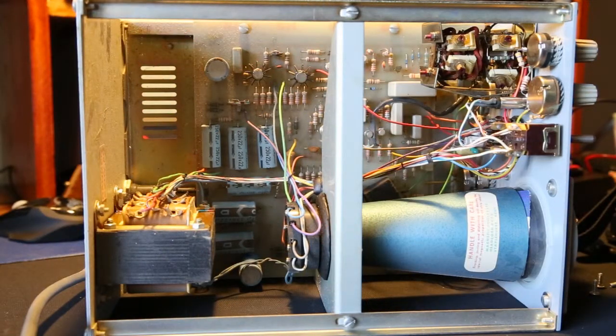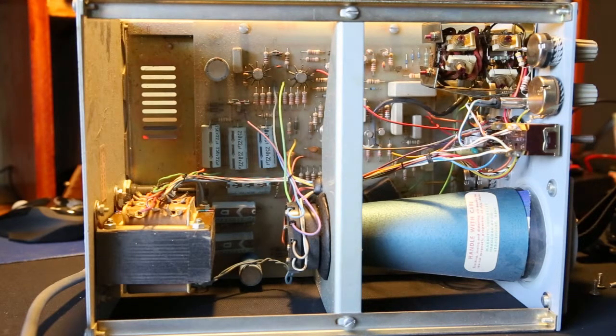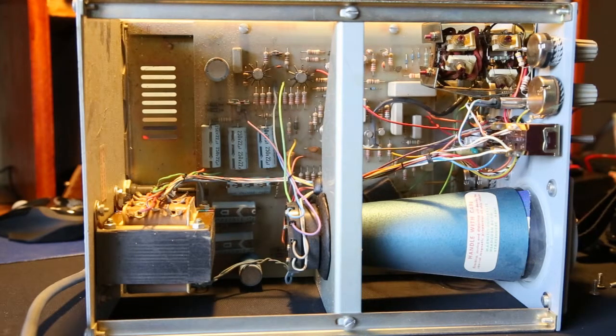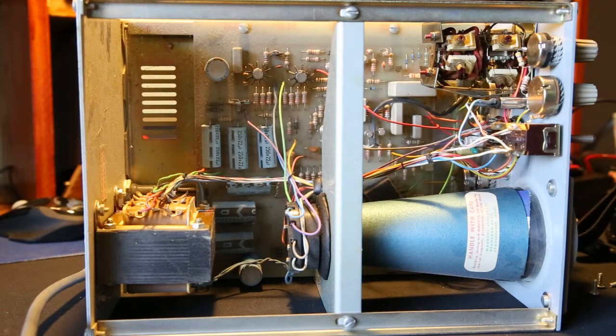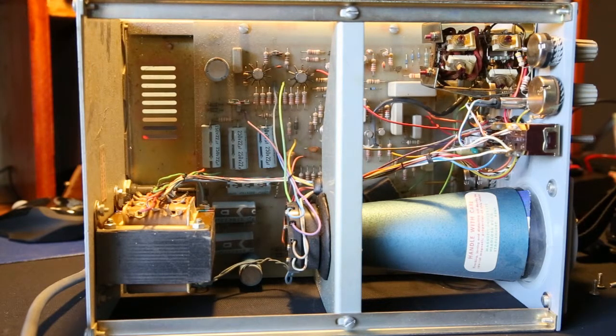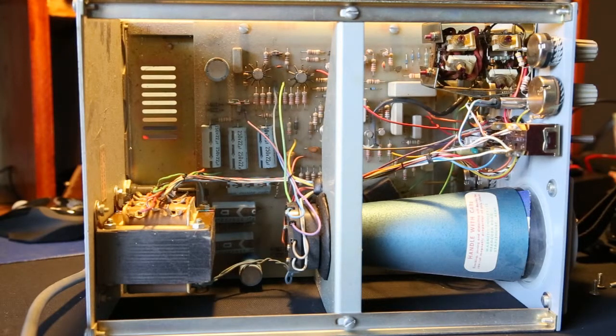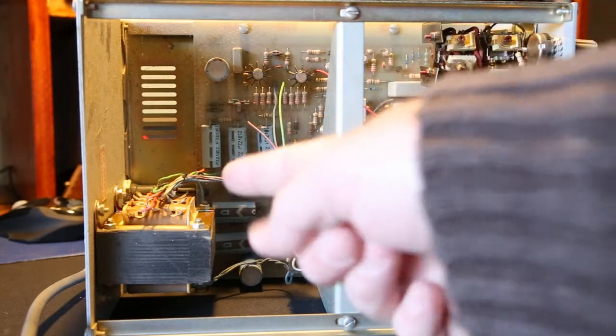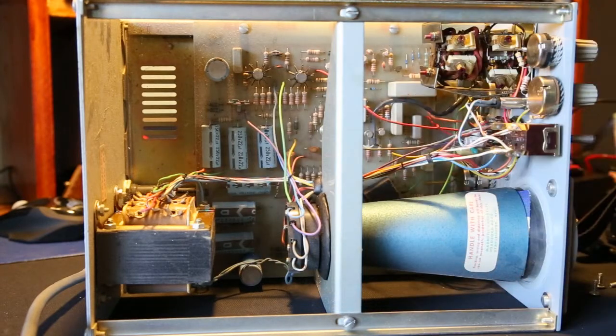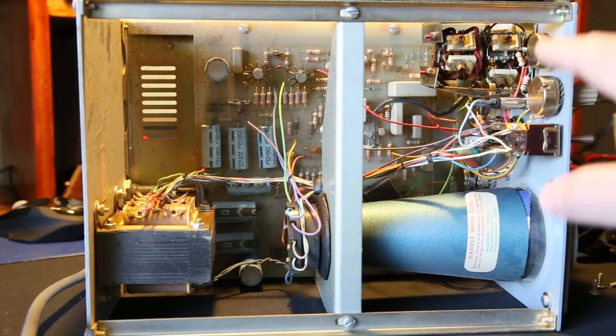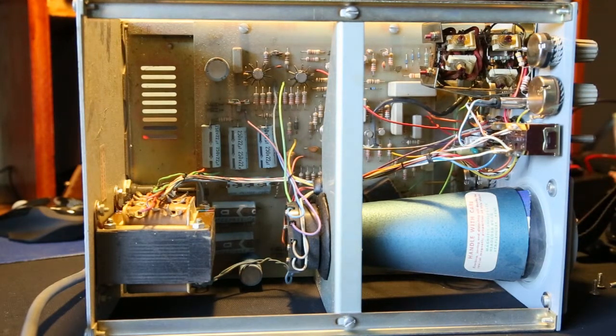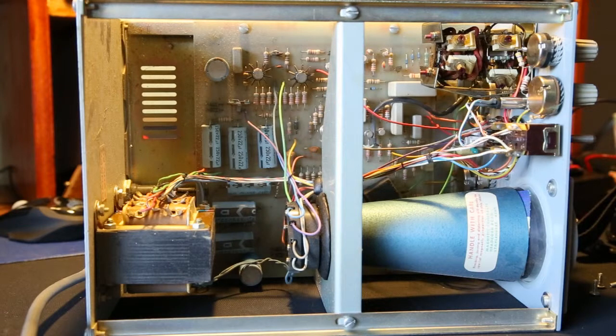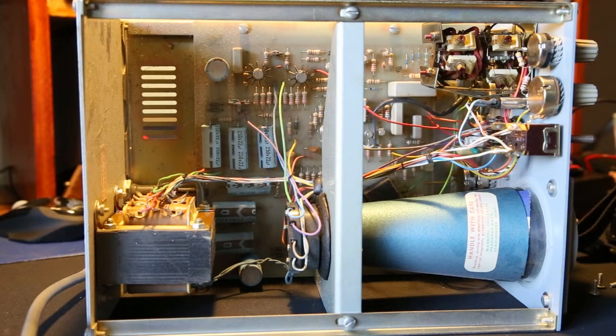Despite what you may think when you first open up these older oscilloscopes with them having very few components inside, they're actually quite nice from the perspective of repairing. I mean, this thing pretty much has very little inside it. You have your power transformer and your main control board, if you will, and most of the actual controls are old style wafer switches and some parts and stuff like that. Not much to go wrong with them. Quite easy to fix if something does.